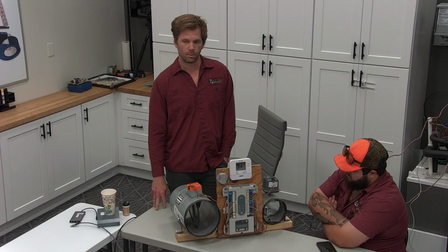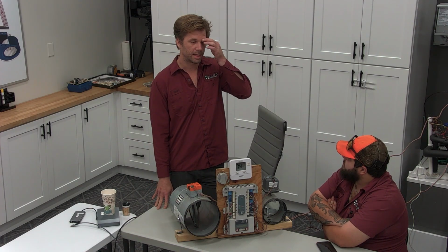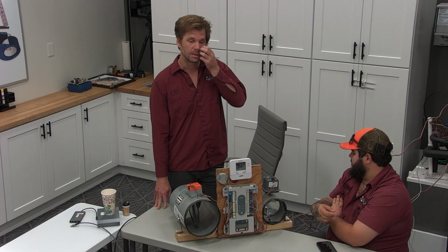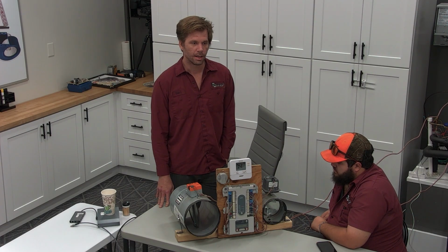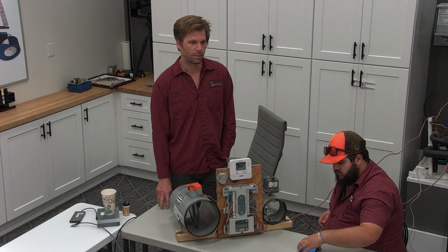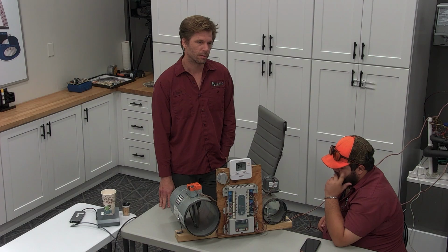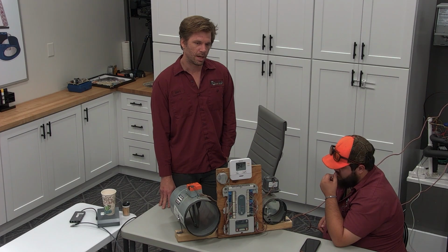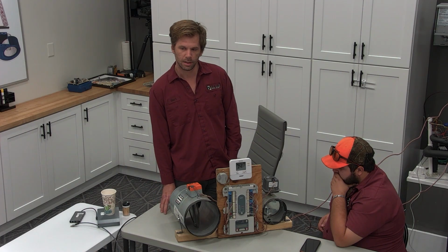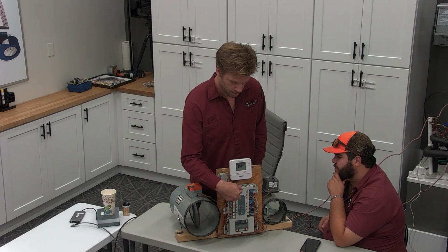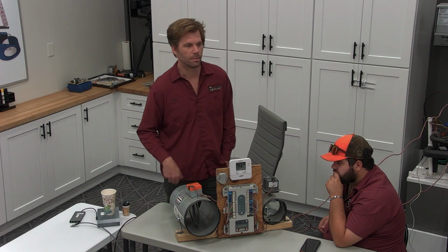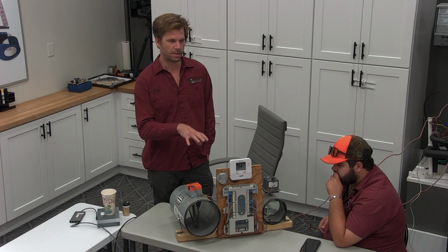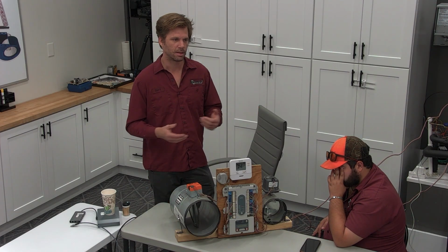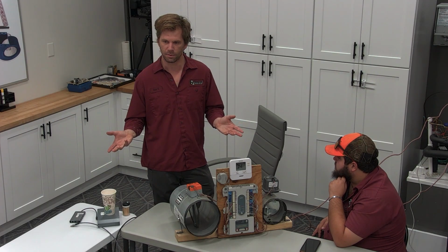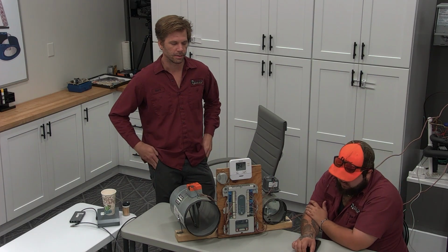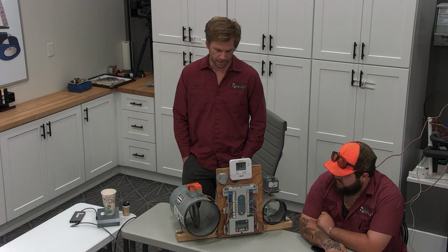So where this becomes a problem is that we haven't properly set it up as a heat pump, or we have one thermostat set up wrong and it keeps energizing the O valve when they're trying to call heat in other zones. So just pay attention when you have issues with heat not calling through the winter. You can configure the damper board for the equipment that you have, and you might have to reconfigure thermostats to match that. Let's try to keep everything consistent. Let's not do a conventional and a heat pump on the same thing if we don't have to. Let's try to keep it consistent throughout the house. So just be aware of that. You will run into that. I got a lot of those calls last year.